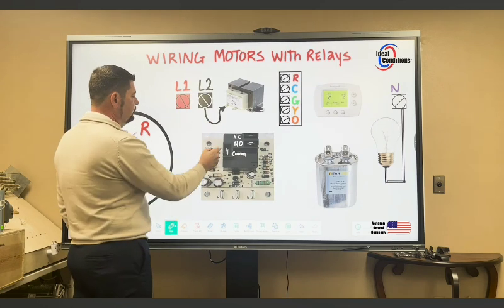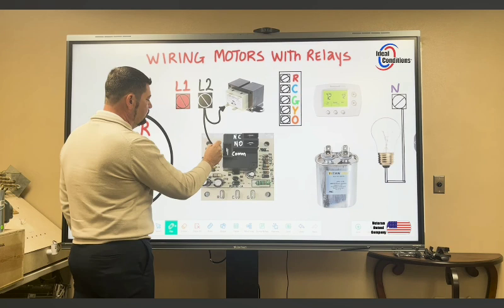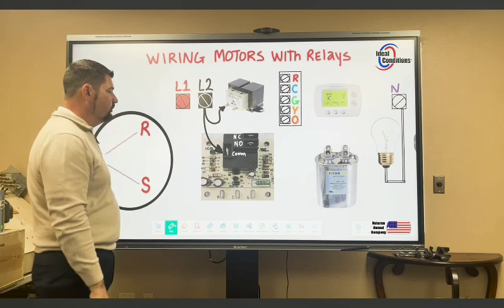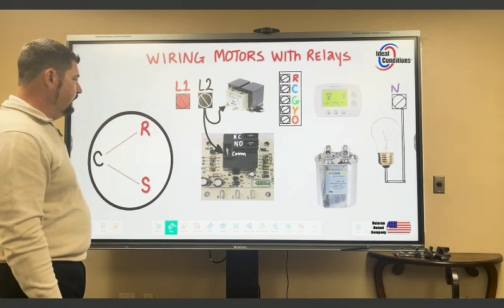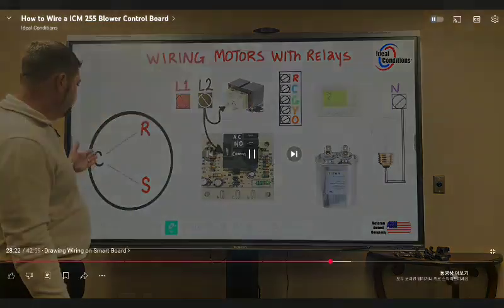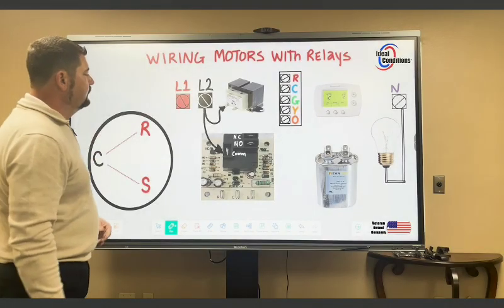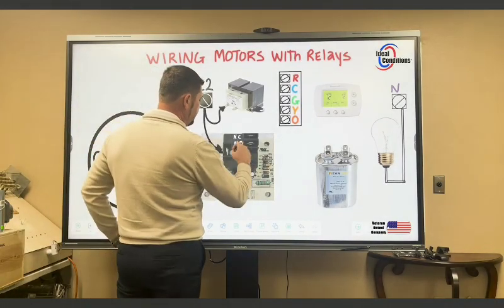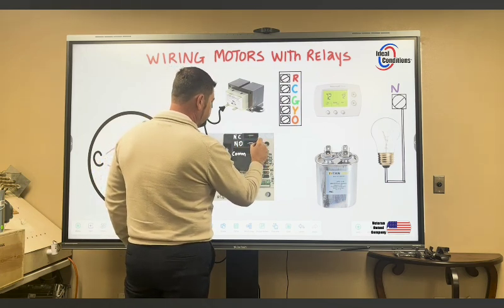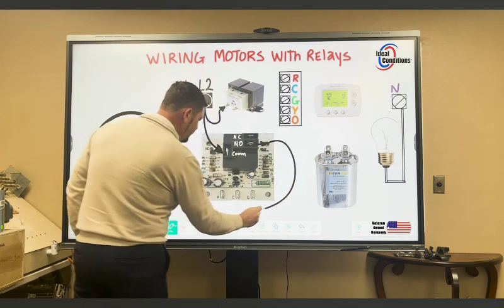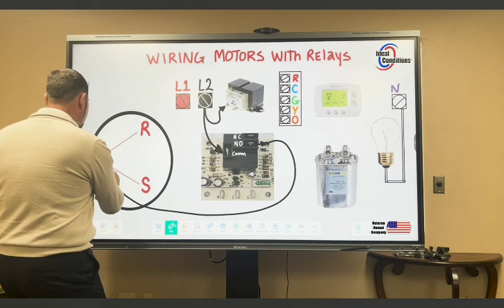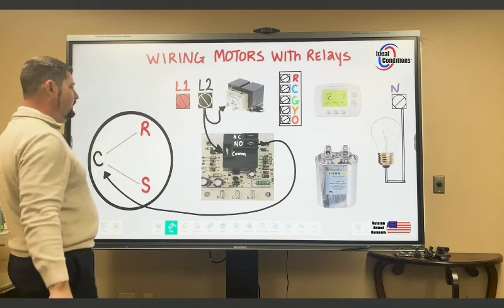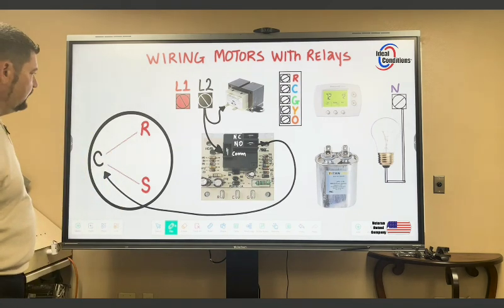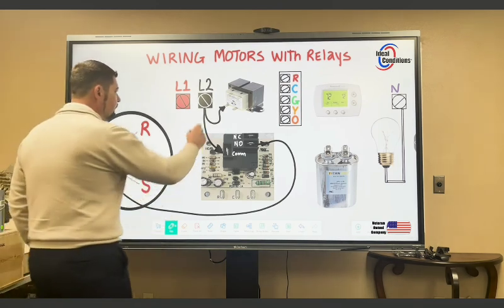Where else do I want L2? Okay, well, I want to wire L2 to my common terminal on my blower relay of my blower control board. And where else does L2 need to go? Well, L2 needs to make it to the motor, but if I want to break L2, I'm going to come off my normally open portion of my relay. So I'm going to just draw an output symbol there, and I'm going to take that over to my common and look back at it and say, okay, what needs to be changed? I think I'm good. Let's go ahead and label them.